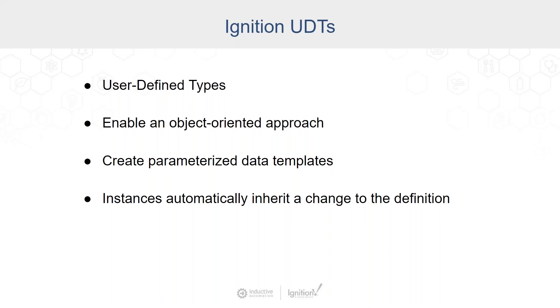When you're collecting data from equipment that comes in as tags, you could just have a flat structure or even a folder structure to represent all of this data as tags inside Ignition. But to follow an object-oriented approach, a better way is to make parameterized data templates or a data model. You take all the tags that are coming and define real-world structures. Every time you have a real-world instance of that object, you want to represent that data in the same way. When you use a UDT, these instances can be based on a definition and automatically inherit any change that you make to that definition.